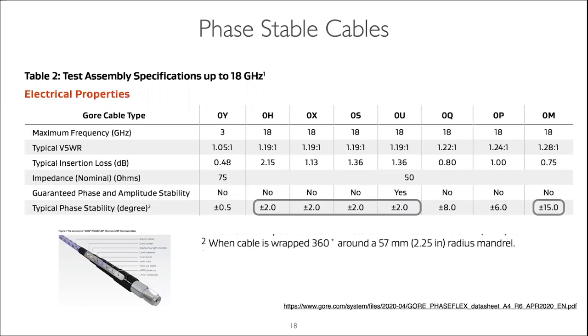I'm not going to talk about tuner calibration, but really quickly, when you calibrate the tuner, obviously you do a coax calibration, and then you want the cables to be very stable. Then you connect it to the tuner. So you're looking for this, plus or minus 2 degrees of stability. But if you're not careful and you use this other version of cable, now you can have plus or minus 15 degrees. Plus or minus 2 degrees at like 18 gigahertz is still decent, but still not nothing. But plus or minus 15, you're talking about like 20-30 degrees. So you can be 20-30 degrees off of your impedance. That's a huge phase shift if you're not careful.